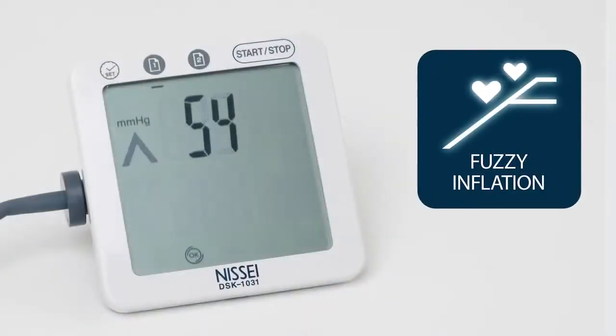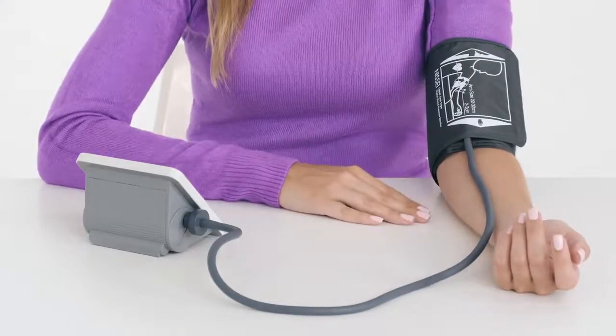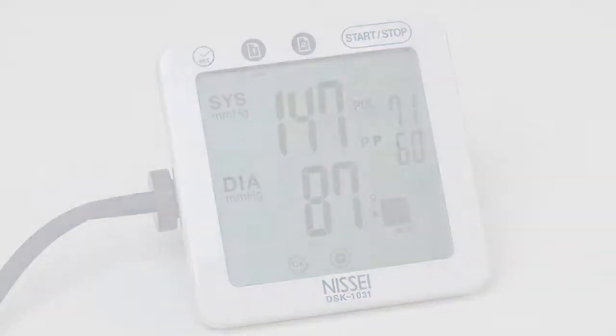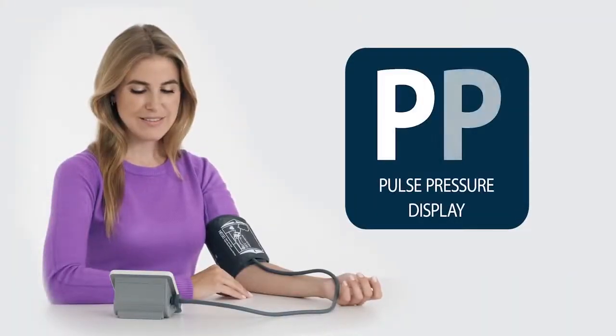The DSK-1031 blood pressure monitor uses fuzzy inflation technology. By measuring pressure in two steps during the injection of air into the cuff, the instrument determines the optimum level of cuff pumping and takes the initial measurement of arterial blood pressure. After the required pressure is reached, the monitor starts bleeding the air and takes the final measurement.